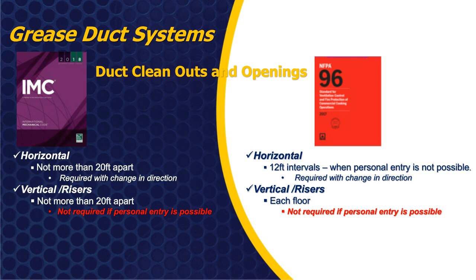Second, if you note, the difference between clean outs can be pretty drastic if the system has any size to it. Here at Schebler, we tend to design for the most stringent, NFPA 96, knowing that if we had the option to remove those, if the local jurisdiction is going to allow us to meet International Mechanical Code, we can pull those out of the system. And also with the thought process is we do coordination of the grease duct system. If there's definitely places in the system where there's no access, we can also consult the local jurisdiction, hopefully remove those out of the system so we reduce the cost of the system and potential points that would be higher risk for any kind of leakage in the system.